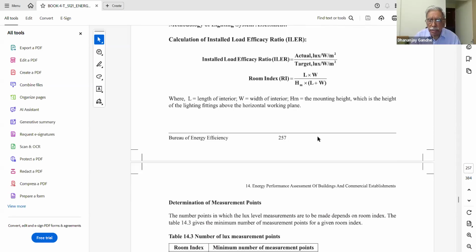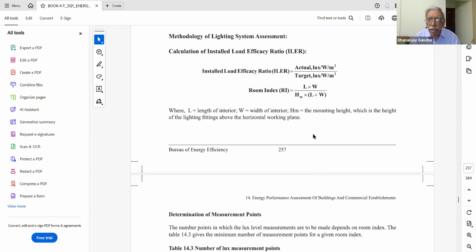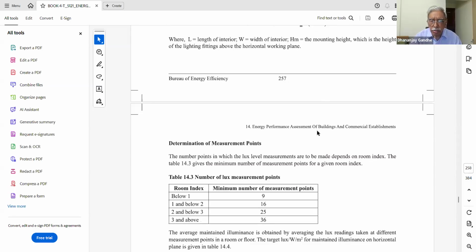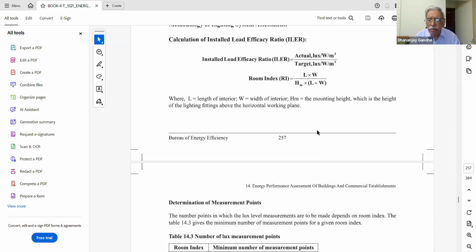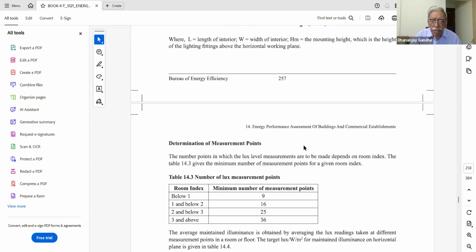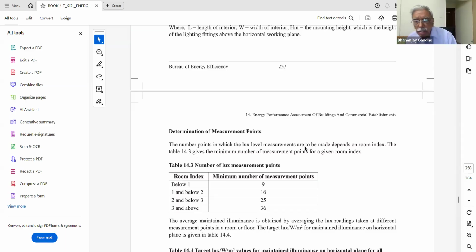Then there is another parameter which also needs to be calculated, the room index. The room index is the ratio of the dimensions of the room: length multiplied by width, divided by length plus width multiplied by height. Basically, it is the length multiplied by width divided by the volume of the space within that room. So this is the room index. For different room indexes, there are different stipulations as far as the lighting power density and the measurements are concerned. The standards specify that, based on the room index, you have to make certain minimum lux measurements at a certain minimum number of points.